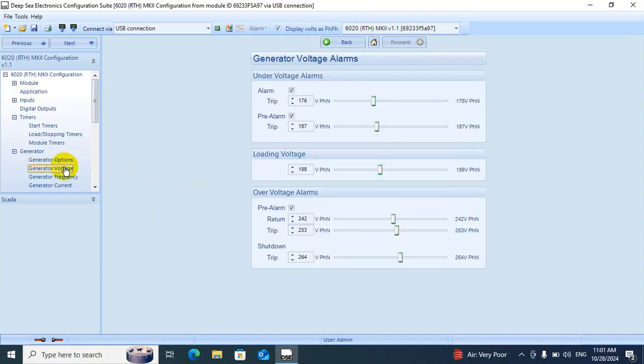In the voltage option, we have the under voltage alarm. This much. We can increase and decrease it, but it's good. Both of them are alarms. Under voltage, because when applying load on the generator, the voltage will decrease. It's the minimum voltage. Over voltage alarm: when the voltage increases to 253, and if it increases to 264, the generator will shut down.